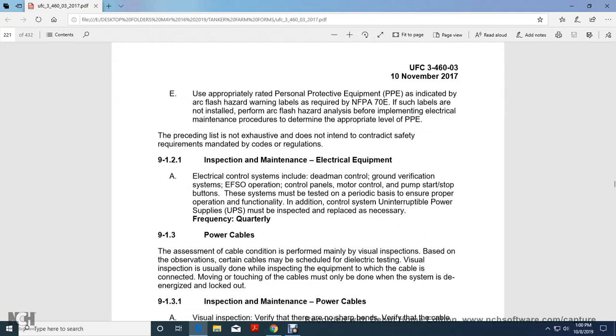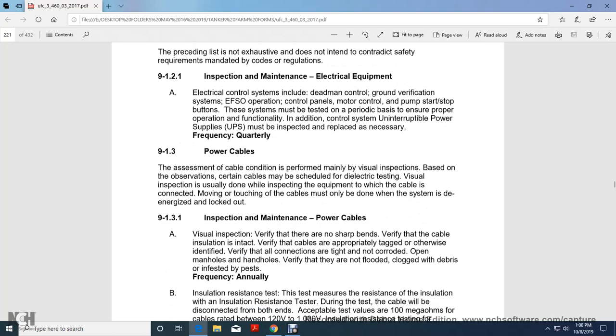Inspection and maintenance of electrical equipment. Electrical control systems include deadman control, ground verification, electrical fuel shutoff valve, emergency fuel shutoff valve operation controls, motor controls, and pump start/stop button systems. These must be tested on a periodic basis to ensure proper operation and functionality. Uninterruptible power supplies included in control systems must be inspected and replaced as necessary, with a frequency of quarterly.